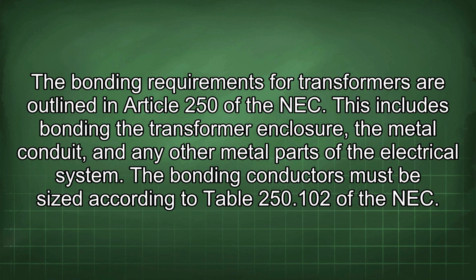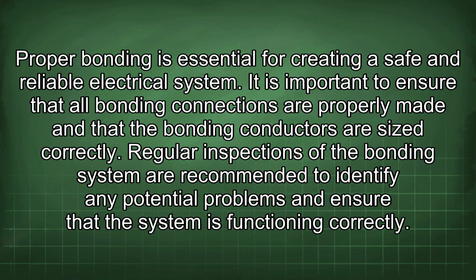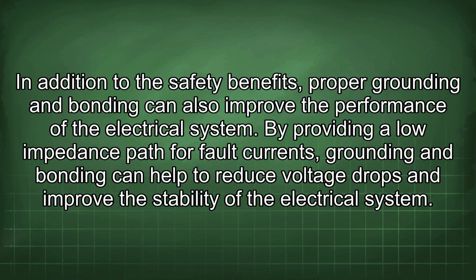The bonding conductors must be sized according to Table 250.102 of the NEC. Proper bonding is essential for creating a safe and reliable electrical system. It is important to ensure that all bonding connections are properly made and that the bonding conductors are sized correctly. Regular inspections of the bonding system are recommended to identify any potential problems and ensure that the system is functioning correctly. In addition to the safety benefits, proper grounding and bonding can also improve the performance of the electrical system.